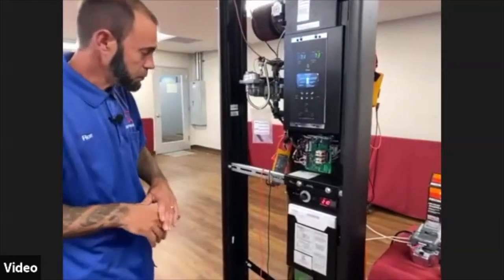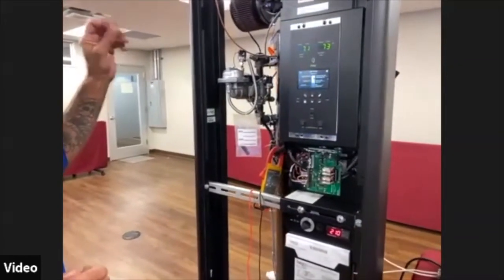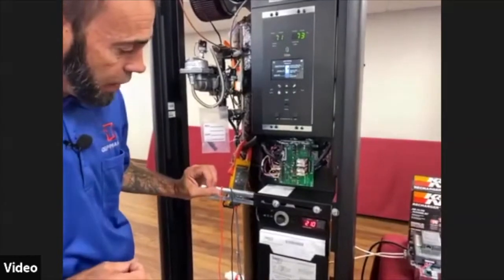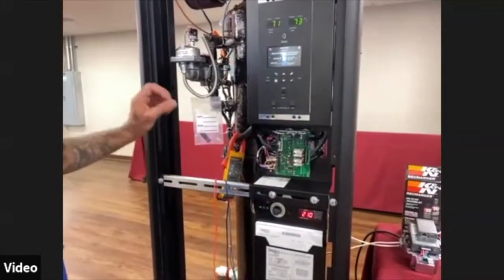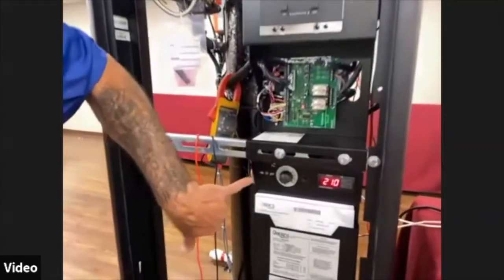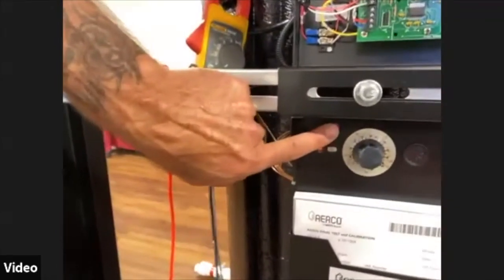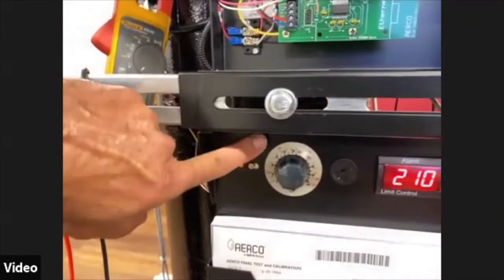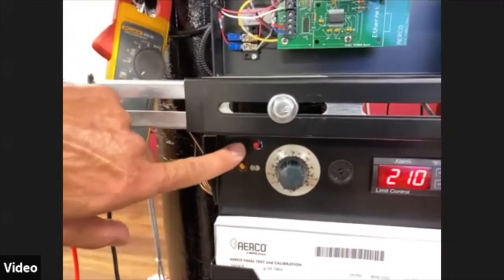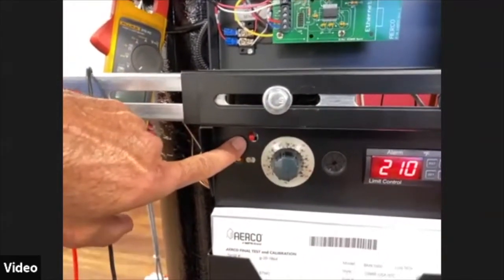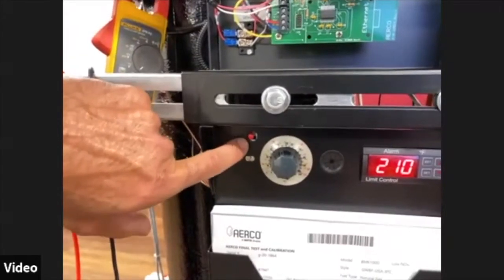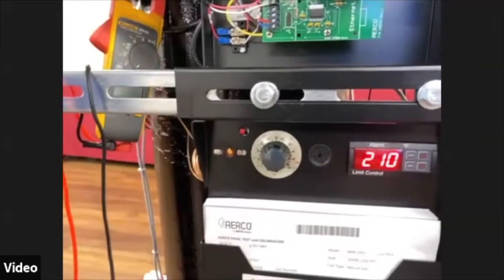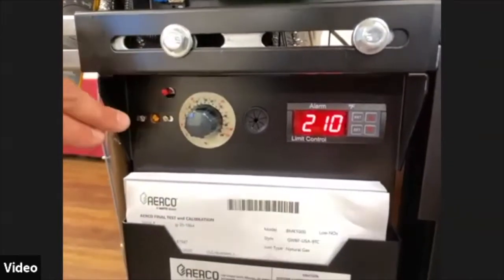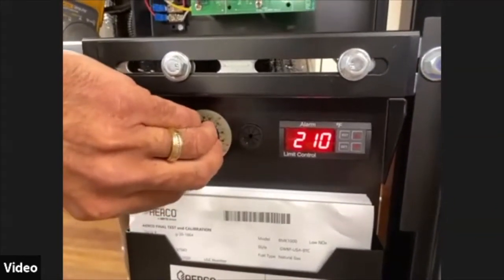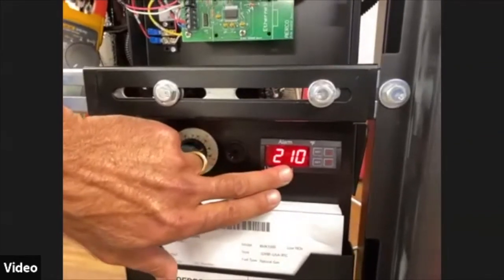Coming back around into the front of the boiler, we talked about the dual temperature controls and our manual resets and operating limits. So our manual reset is actually right here. And this does have to be manually reset. So if you get a fault on a high water temperature, high water outlet temperature, you will probably have to reset this. You can't just clear the fault on the screen. This would be our operating limit, and this is our low water cutoff control.